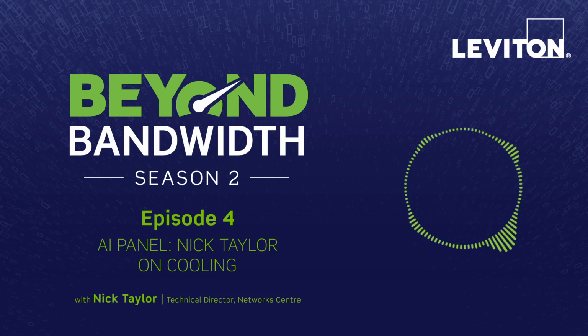This is what we see in the vast majority of data centers. There are some different versions of hot aisle containment, often called chimney racks or vertical exhaust duct racks, where if people want to deploy a rack at a time, they can do that. But again, we don't really see that much in the UK anymore. It tends to just be hot aisle containment.